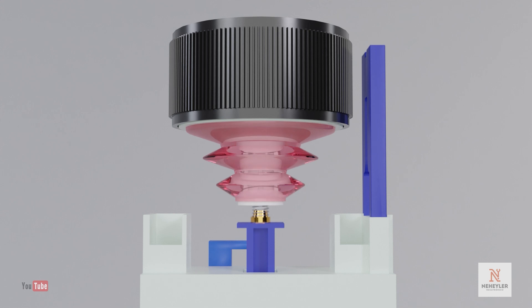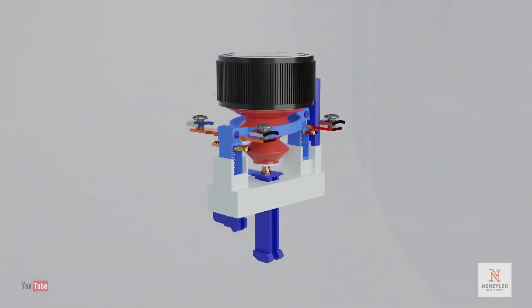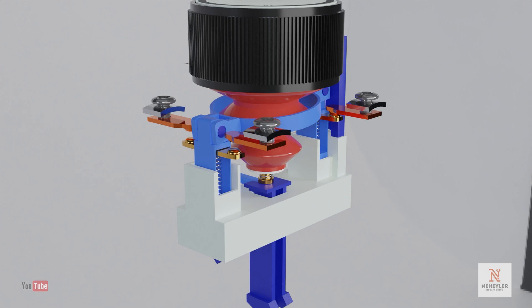When the latch is retracted, it pushes the moving tip back to its starting location. And this is how a mechanical pneumatic timer works. That is why it is said that no electrical energy is needed to carry out the timing, since it works by spring deformation and air in the bellows chamber.